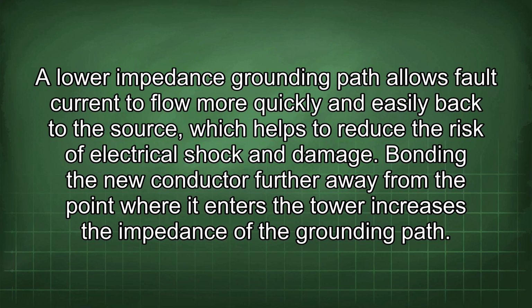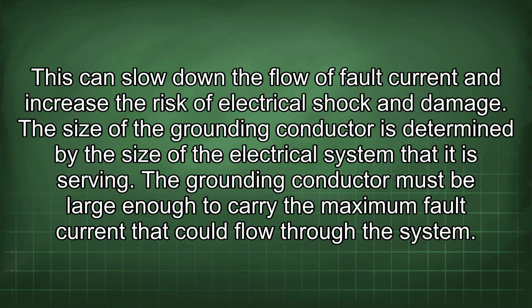Bonding the new conductor further away from the point where it enters the tower increases the impedance of the grounding path. This can slow down the flow of fault current and increase the risk of electrical shock and damage.